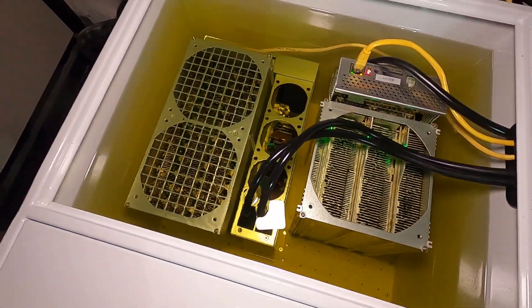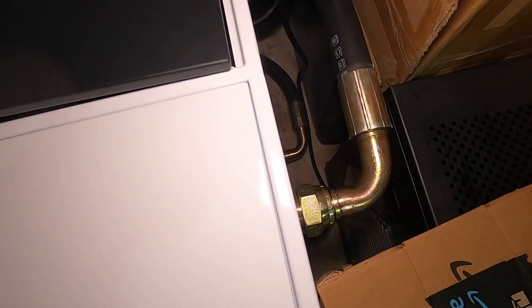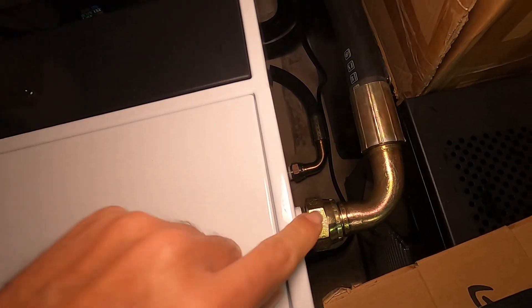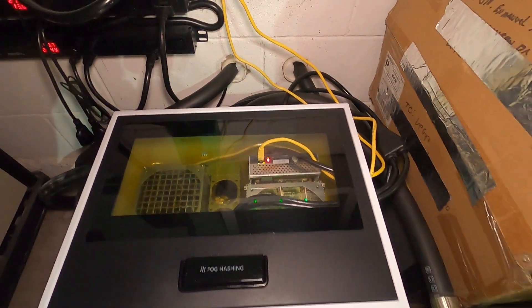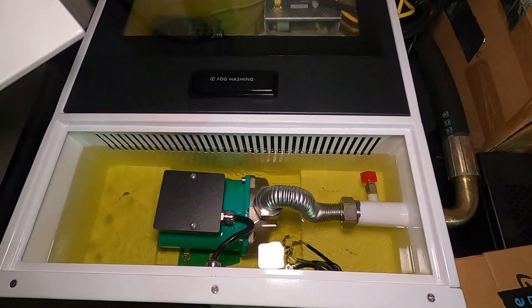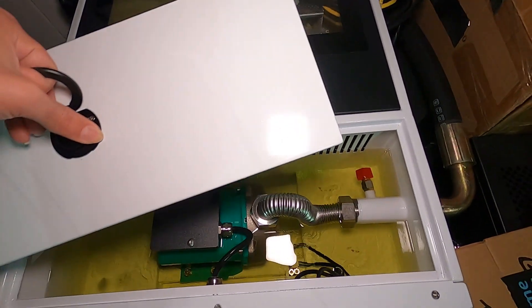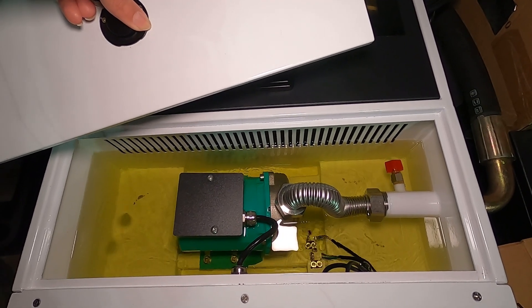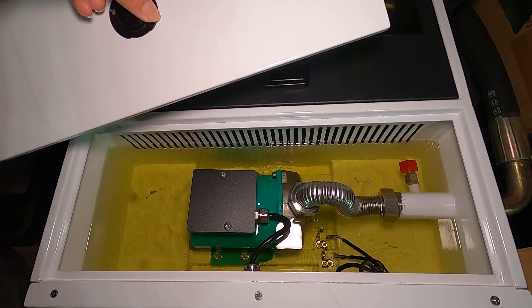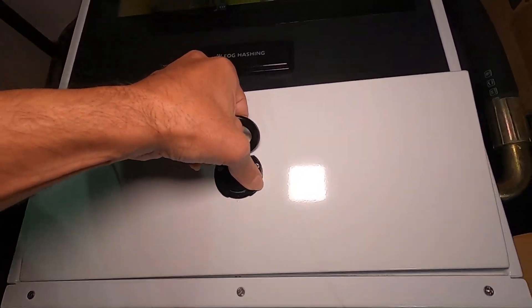I don't think it's either of those — I think it's the fittings. Over here on this corner you can see we have brass fittings, but the problem is these 90s wouldn't fit through the two-inch holes back there, so we had to replace them. The color has not gotten darker yellow, so it could be that the individual who changed out the fittings used a little bit of extra grease, and this might be that grease now in the liquid.